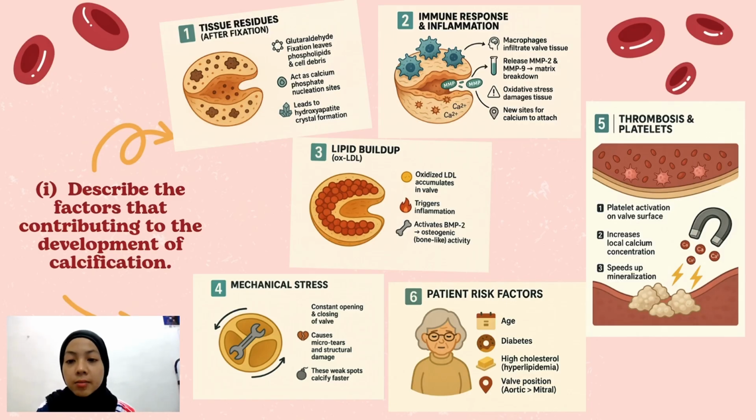First, we describe the factors contributing to the development of calcification. There are 6 factors. First, tissue residue. Glutaraldehyde fixation leaves phospholipids and cell debris that act as calcium phosphate nucleation sites, leading to hydroxyapatite crystal formation. Second, immune response and inflammation.